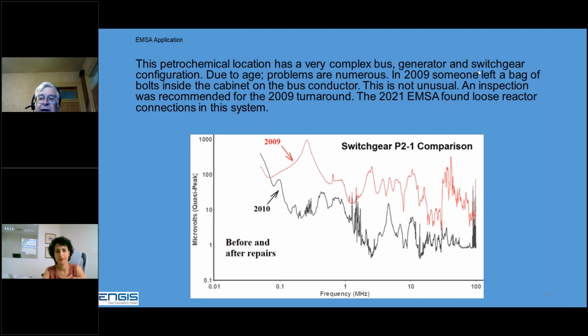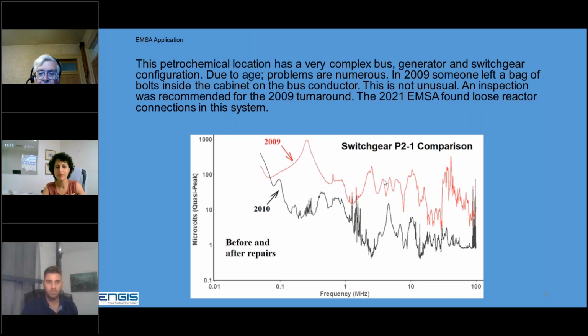In 2009, somebody had left a bag of bolts, plastic bag of bolts, inside the cabinet on top of the bus conductor. And that's what we got here on this P2-1 switchgear. We got all of this arcing, and it was a bag of bolts laying on the bus conductor. They opened it up, they found the bolts, they took them out, and of course in 2010 it was down to where it should be.